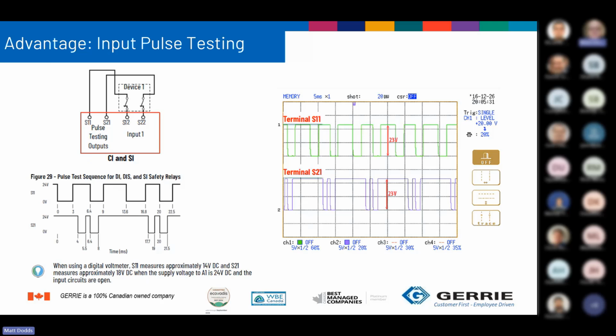Advantage over electromechanical relays: safety input pulse testing. So on the bottom left-hand side there, you see that S11 puts out a series of pulses, and S21 puts out a different series of pulses. So then the input terminals S12 and S22 are looking for those pulses, right? If it sees an open, a short to ground, a short to positive, or anything, it will fault out and give you an error on either channel.